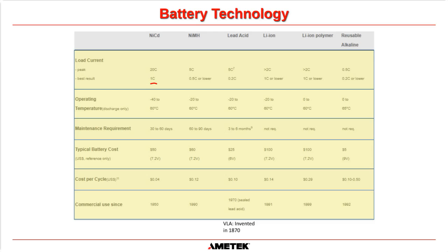What we're saying is for a NiCad, you can get 1 times, so basically you can get the full ampere capacity out of that battery without any issues, okay? For a lead acid battery, they're saying it's 0.2. Now, once again, I've said that I'm not a battery expert. These numbers, what I would say is don't look too much into what these numbers mean, but look at the ratios between each one. So basically we're saying you're going to get 5 times more current out of a NiCad battery of the same ampere hour as a lead acid battery. It doesn't matter what the ampere hour value is. Basically we're saying you can get 5 times more current out of a NiCad than a lead acid. And once again, you can get 5 times more out of a lithium ion than a lead acid. Okay.